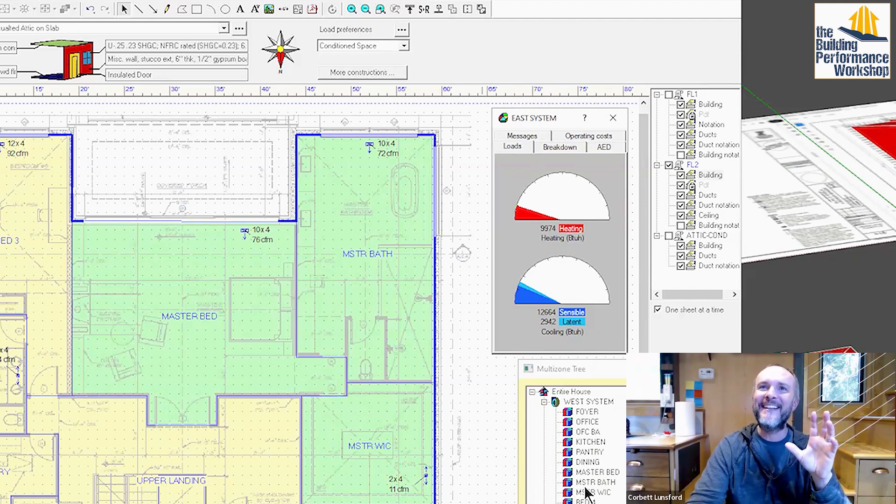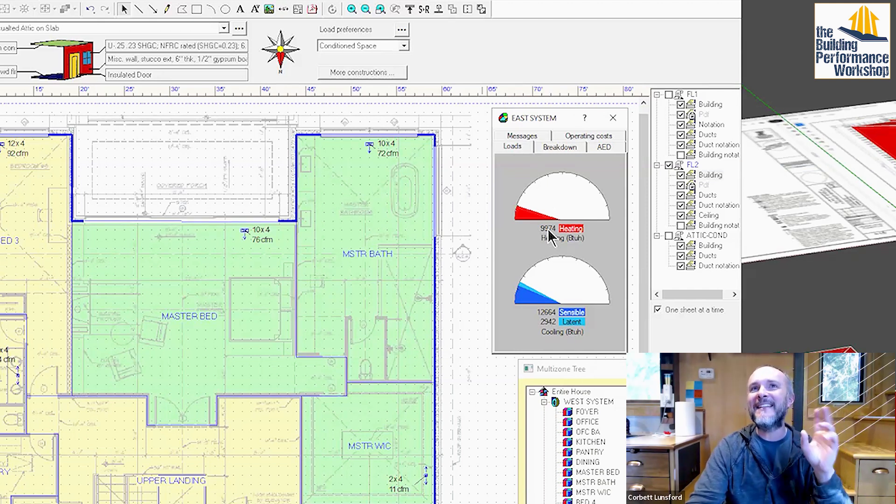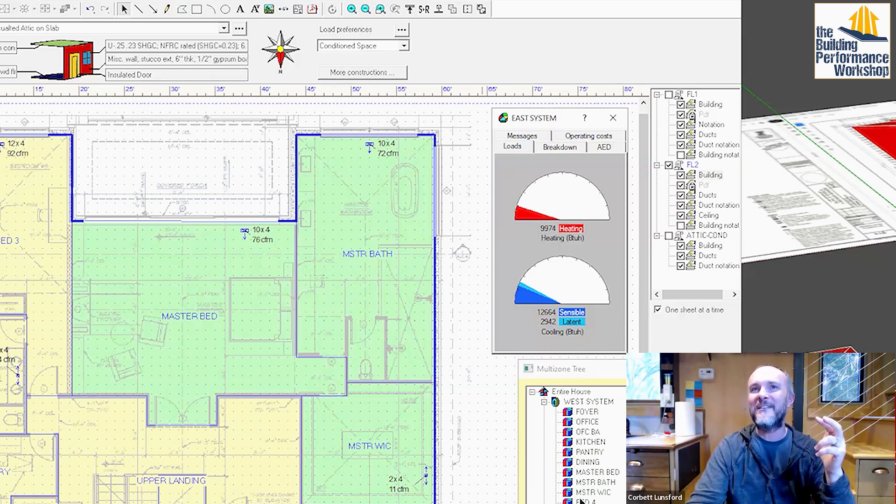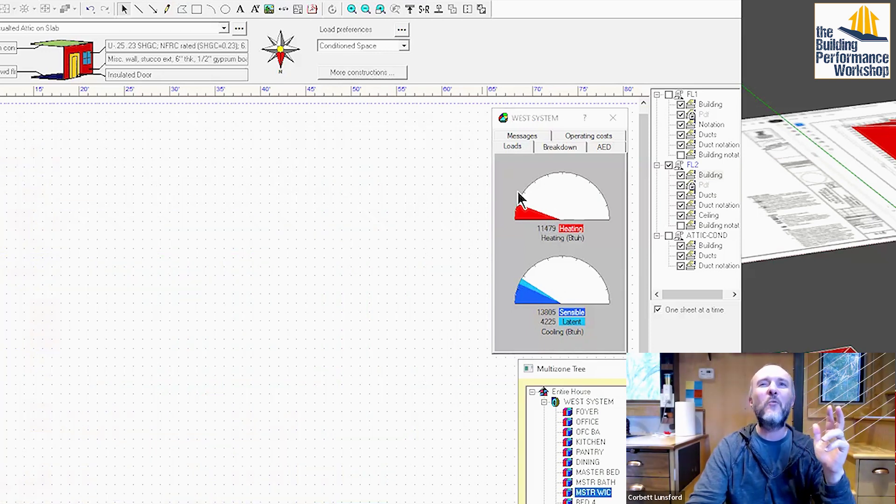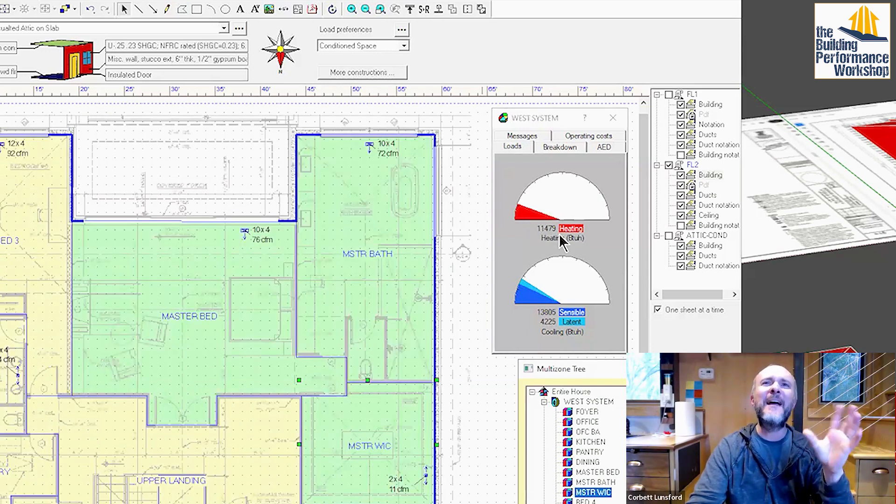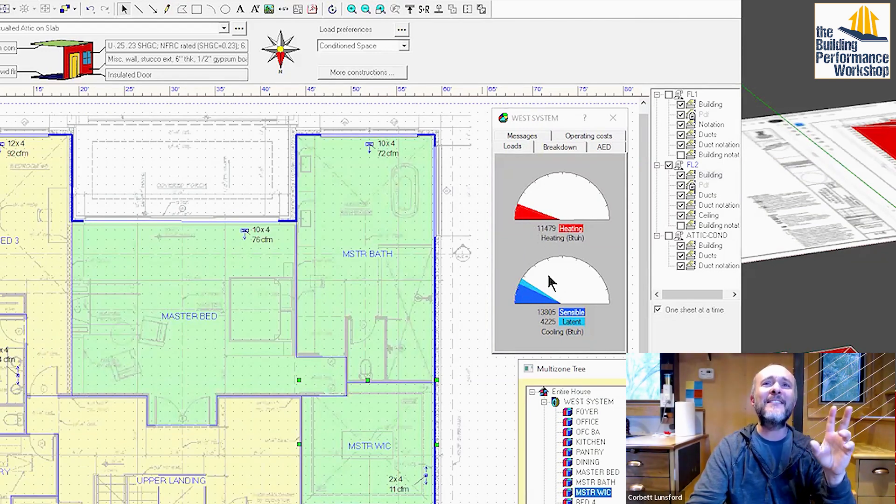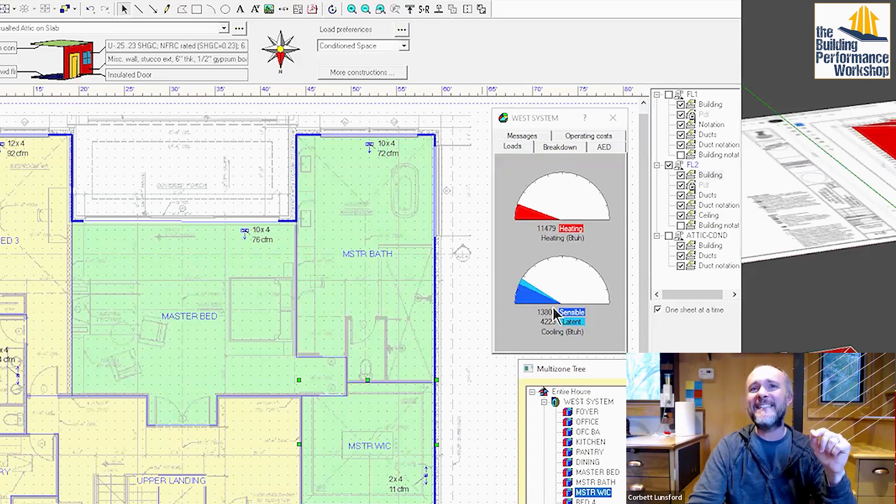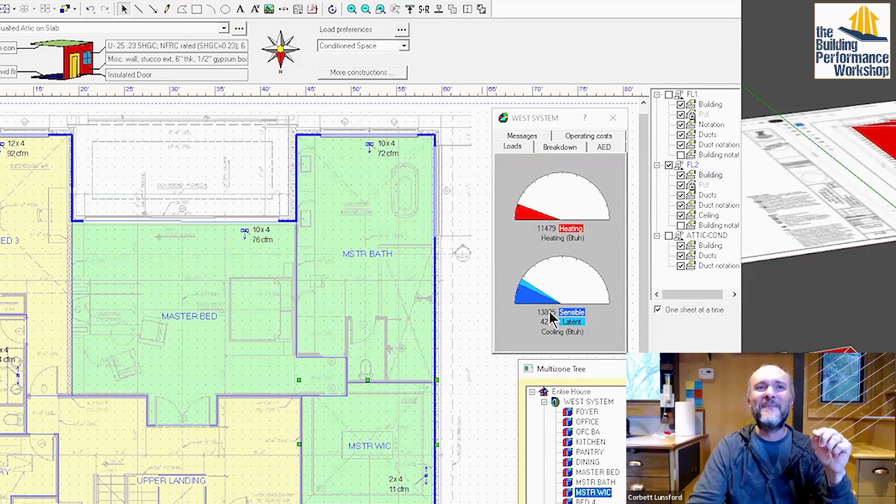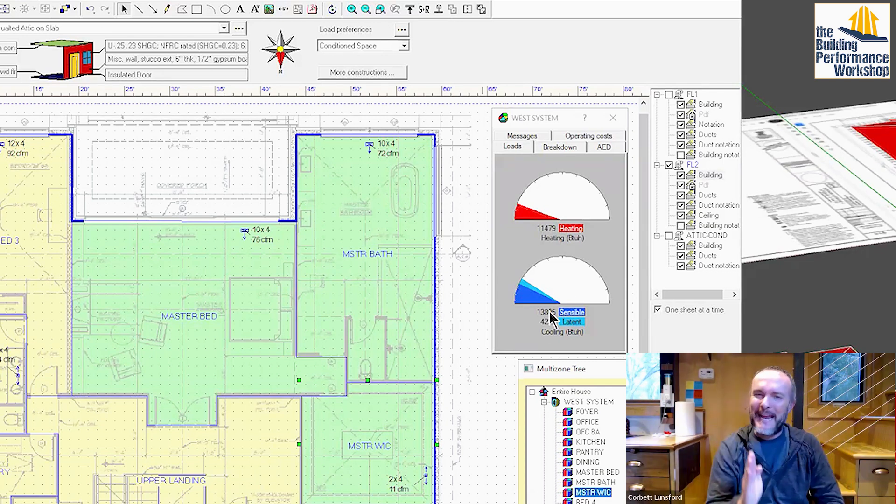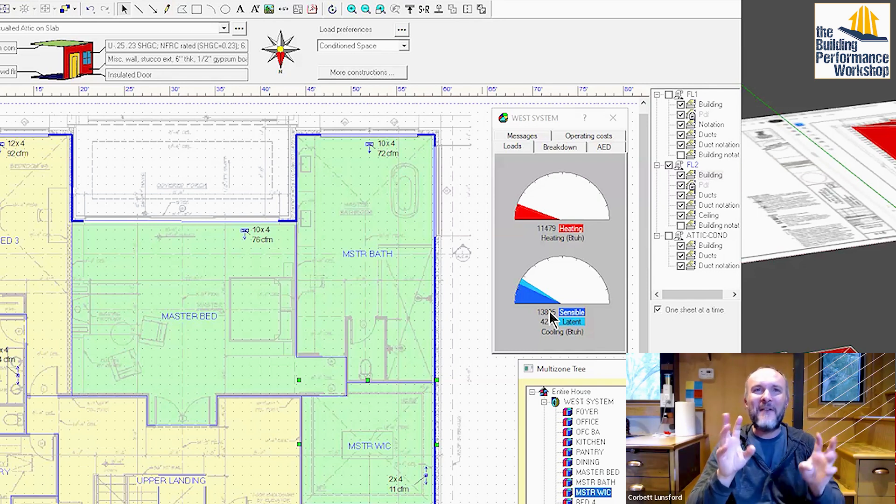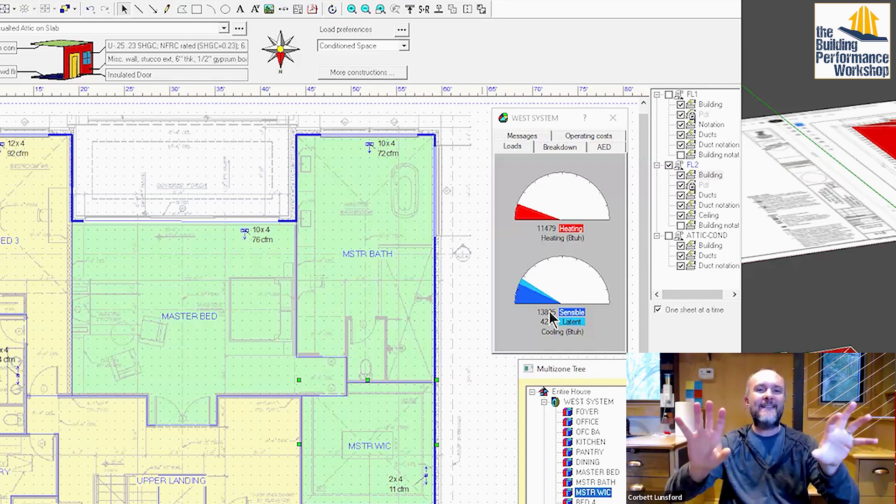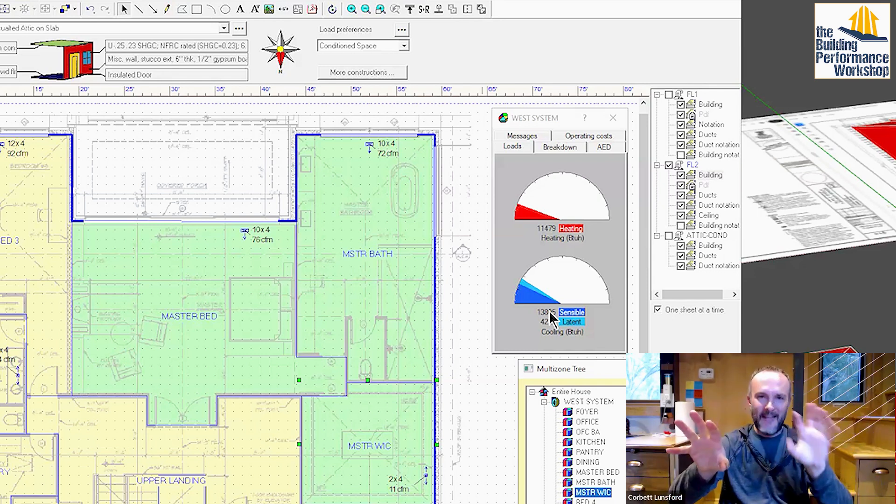The east side system has about 10,000 heating needed and about 14,000 of cooling needed. West side system, about 11,000 and about 15, 16,000 here. So that is splitting it right down the middle. Now we have two completely identical systems left and right that we can put into this house.